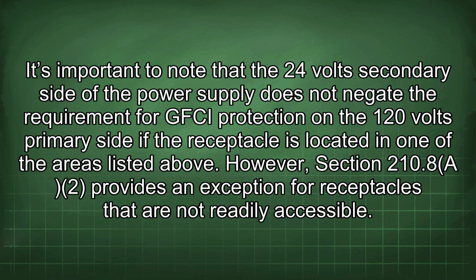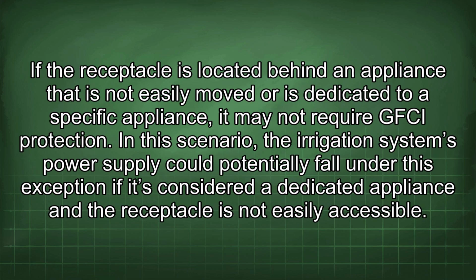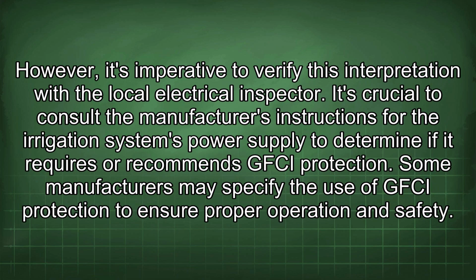However, Section 210.8(A)(2) provides an exception for receptacles that are not readily accessible. If the receptacle is located behind an appliance that is not easily moved or is dedicated to a specific appliance, it may not require GFCI protection. In this scenario, the irrigation system's power supply could potentially fall under this exception if it's considered a dedicated appliance and the receptacle is not easily accessible. However, it's imperative to verify this interpretation with the local electrical inspector.